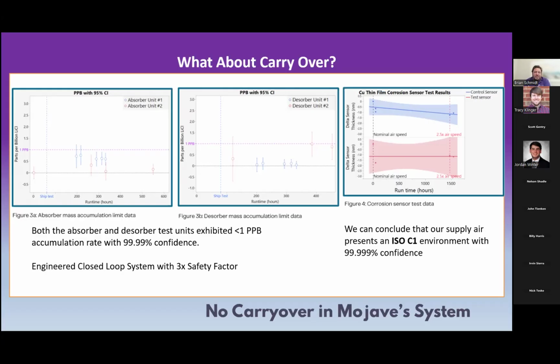So what we like to call this is an engineered closed loop system. It is open loop in terms of, again, the air does directly touch the liquid desiccant, but we're really, really good at keeping that liquid desiccant on the pad and not sucking any of it downstream. So we call it an engineered closed loop system. We have a 3x safety factor on the face velocity. So what we're limited to with our airflows is based on the size of the pad itself. There's only so much of this liquid desiccant the pad can hold, right? And if we're pulling air through the system too quickly, we're going to increase our potential of carryover. So we keep our face velocity very, very low. And there are some other geometry features of the pad itself that provide the ability to keep the liquid desiccant on the pad and in the system and not have any of this carryover.